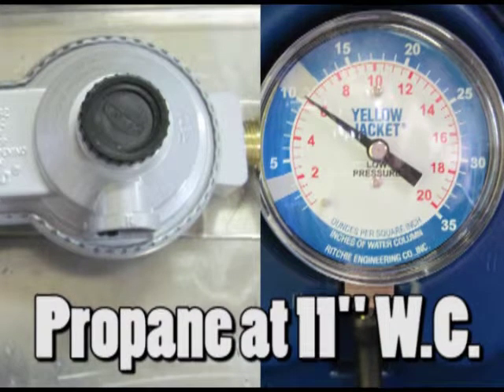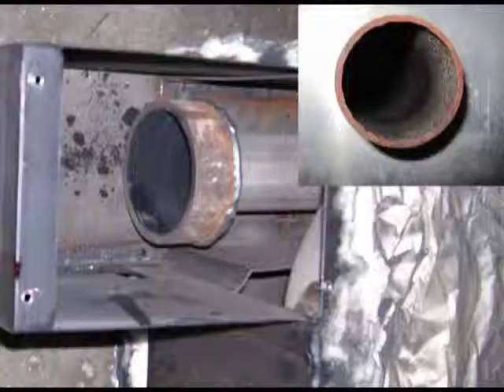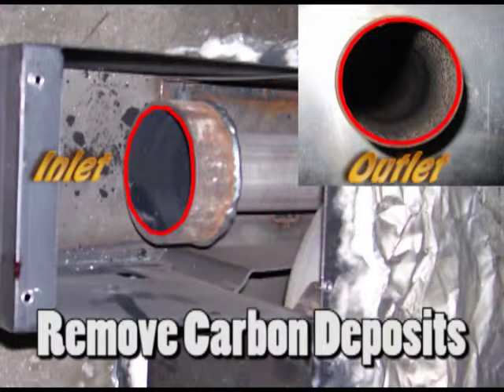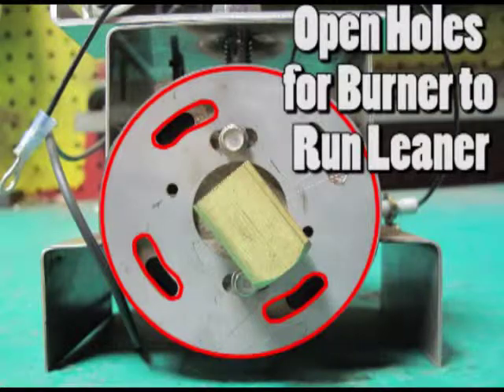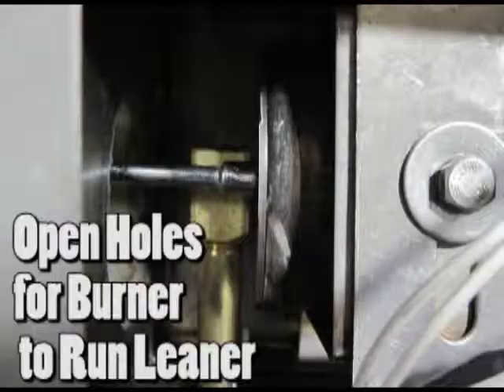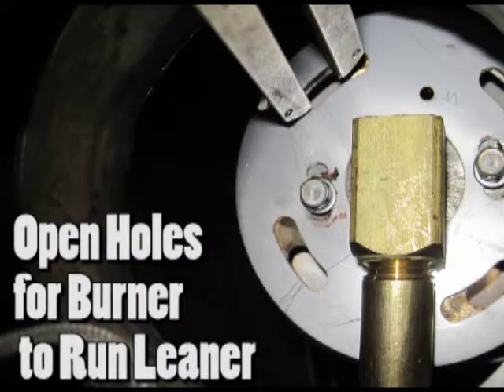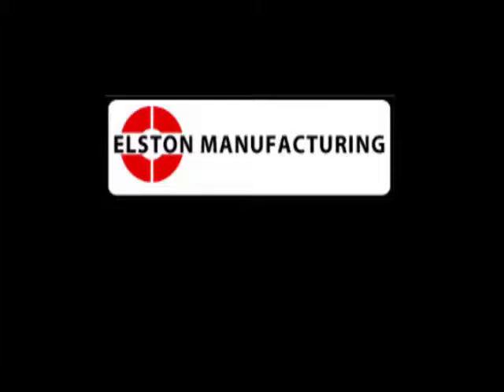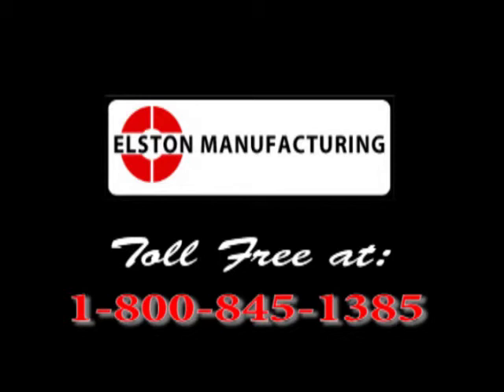Therefore, it is necessary only if you have no records that it was done during installation or it has been a few years since the heater was installed. After you have corrected the problem, remove any carbon deposits present in the exhaust tubing. If problems reoccur, the air adjustment disc can be adjusted such that the heater will run leaner. Please consult us at Elston Manufacturing for additional information. Again, Elston Manufacturing's toll-free number is 1-800-845-1385.